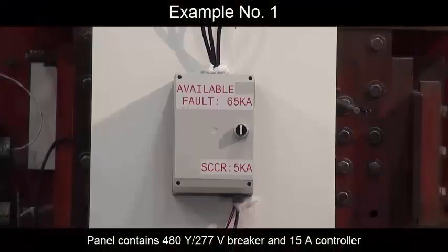In this example, the controller is not suitably paired with the proper overcurrent protective device, and the overcurrent protective device has an insufficient interrupting and voltage rating.